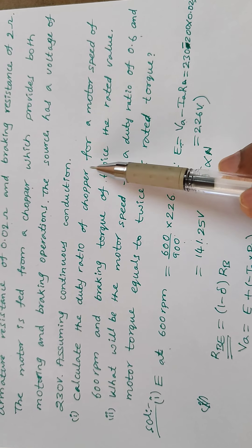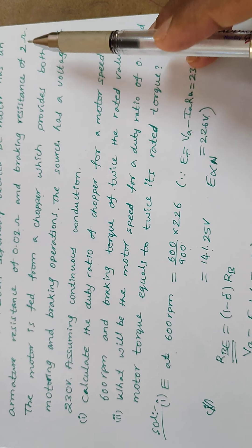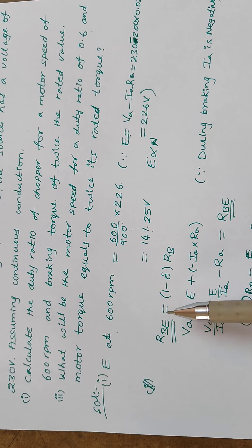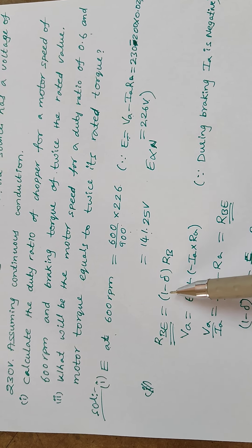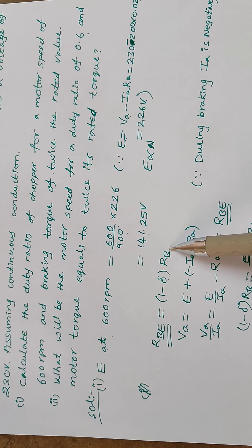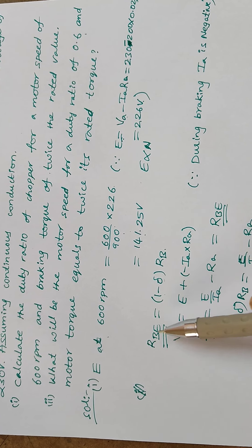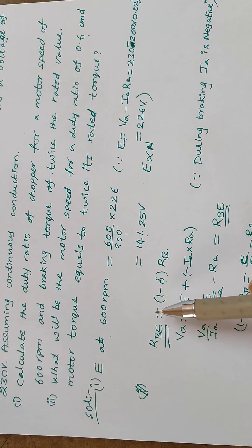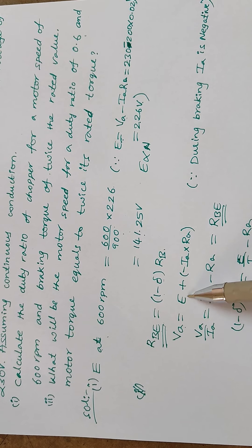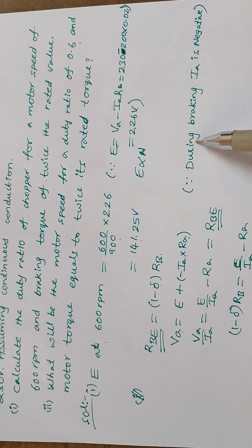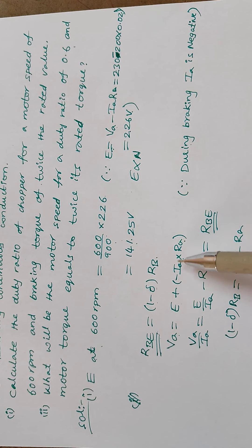Now we need to find the duty ratio of the chopper. The braking resistance is 2 ohms. The effective braking resistance Rb_eff equals (1 minus δ) times Rb. To find the effective braking resistance across the armature terminals, we can also use Va equals E plus Ia times Ra for motoring mode. But since this is braking, Ia is negative, so it becomes E minus Ia times Ra.